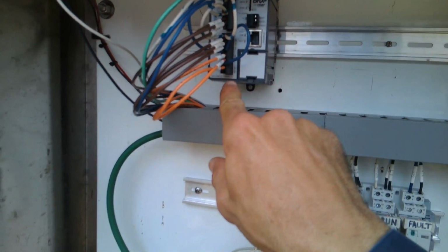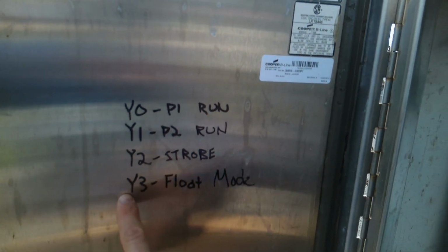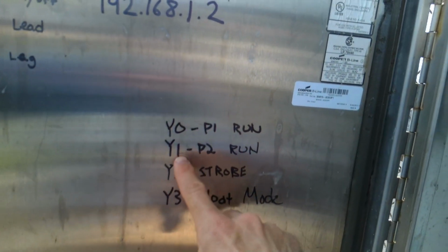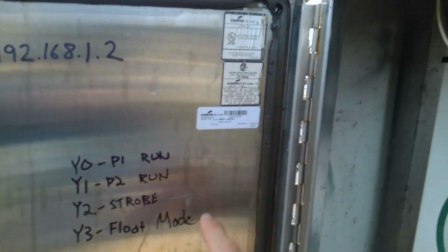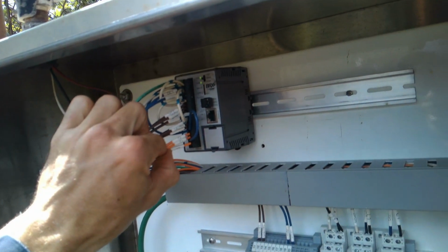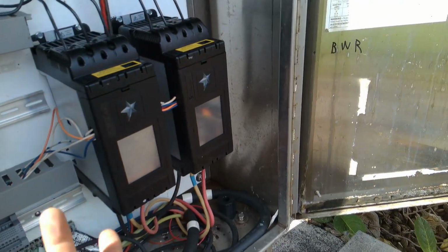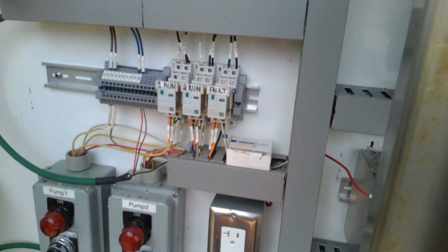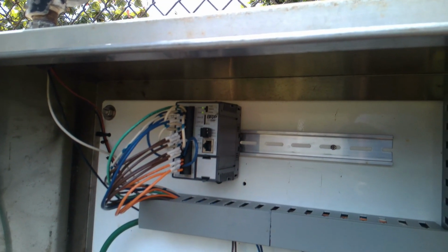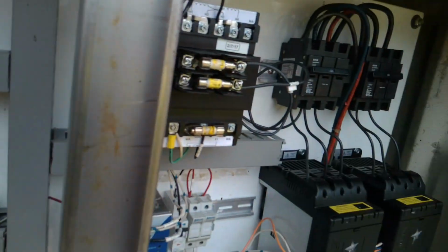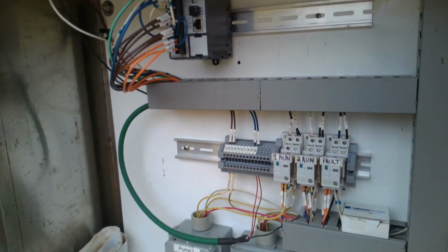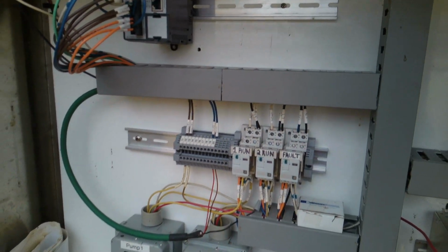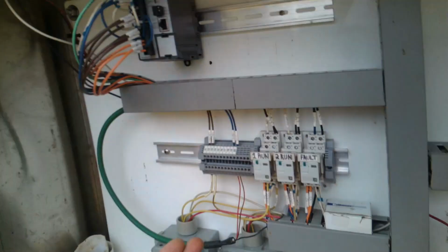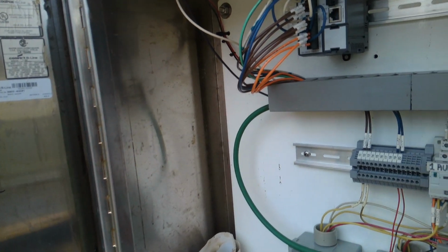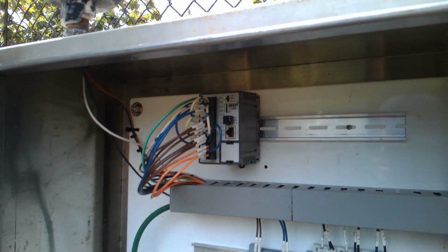Okay, so when Y3 is lit up, see I don't have anything landed there, but I just made it an indicator for float mode. Y2 goes to the strobe, and Y1 is pump 2 and Y0 is pump 1. So here's our relay outputs from our PLC. They fire these relays, which tell them to start. I did just hear something click. That was odd. Yeah, I want to connect my laptop and see what the PLC is seeing as far as what the transducer level is. I want to see that live. I could connect my transducer troubleshooter to it. Oh yeah, look at that.